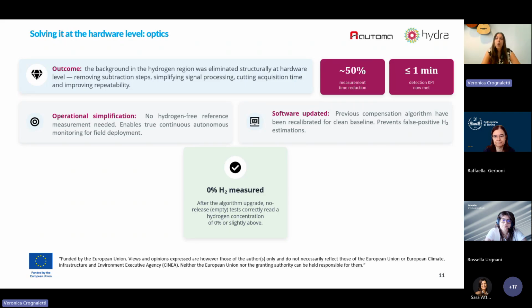In addition, we also added a software update, because the previous compensation algorithm that we introduced has been recalibrated for the clean baseline. So now we don't need a hydrogen-free reference measurement, and we are able to do this type of measurement also in free air, where we cannot know whether hydrogen is there or not. And we also have a reduction of the measurement time.